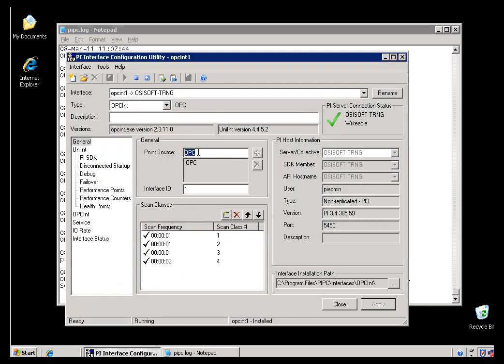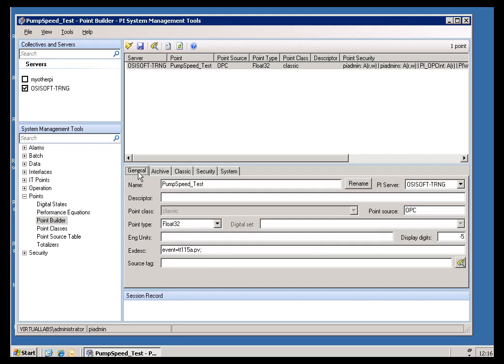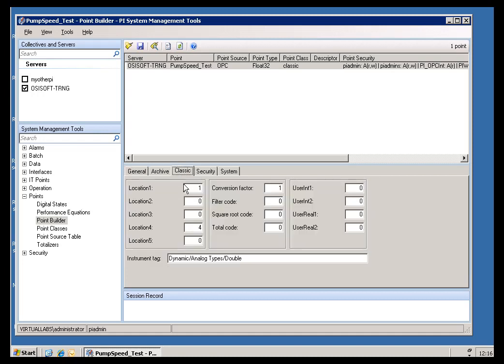It's looking for the Tags that have this Point Source and this Interface ID. That Interface ID is normally put in Location Code 1 in the Point Definition, so let me bounce back to the PI Server. We can see that this Tag does match. It does have the Point Source of OPC, and if I look at the Classic Tag, Location 1 is equal to that Interface ID number. On the surface, this looks like it should work. I can't really figure out what the problem is here without going back to that Log.